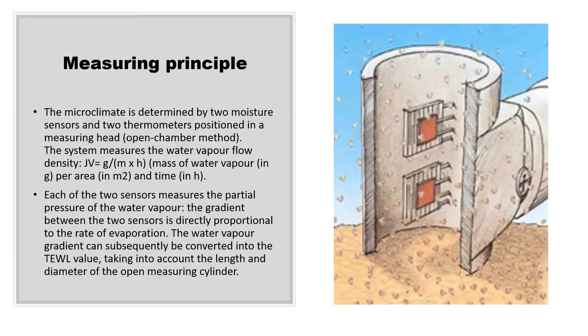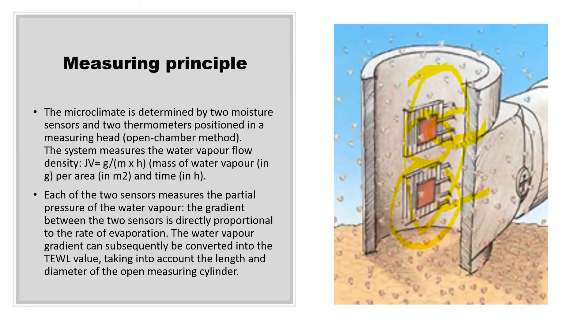The TEWL equipment has a probe which is placed on the skin body part. The microclimate is determined by two moisture sensors along with a thermometer positioned in a measuring head — this is the open chamber system. It measures water vapor flow density per unit area per unit time. Each of the two sensors measures the partial pressure of water vapor and the gradient between the two sensors, which is directly proportional to the rate of evaporation. The computed digital value is then displayed on the monitor, and at least three values are taken to calculate the mean.